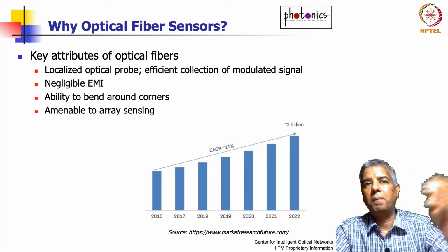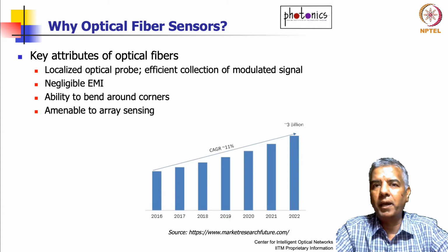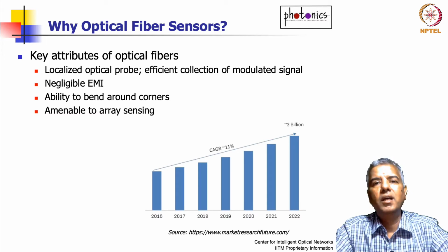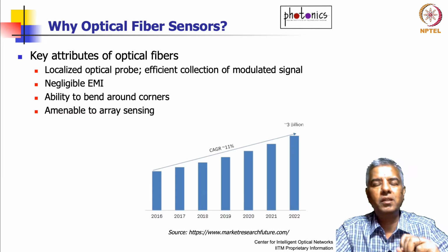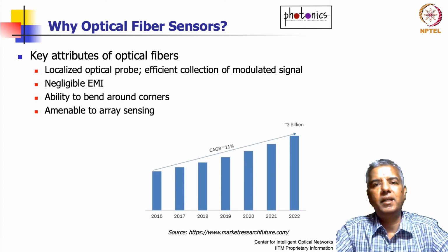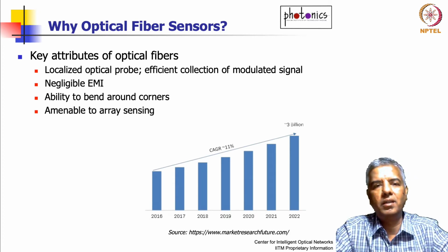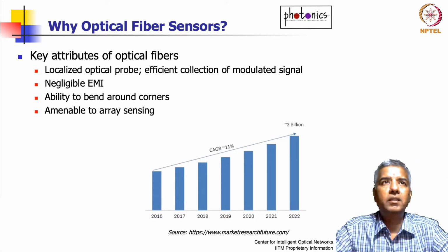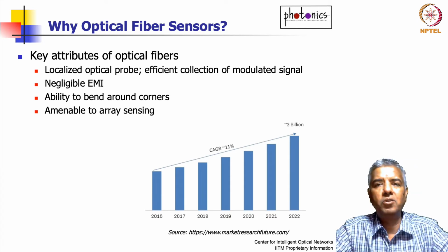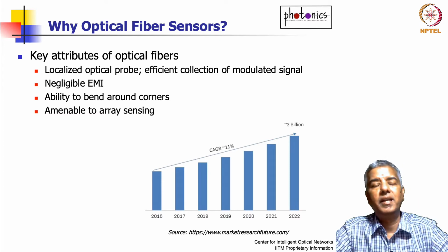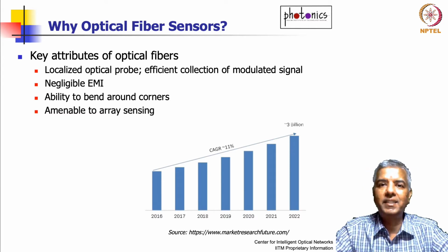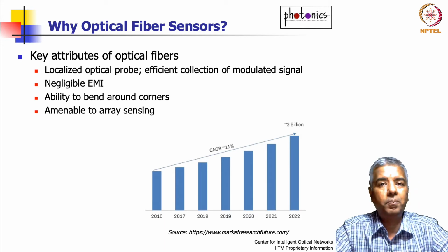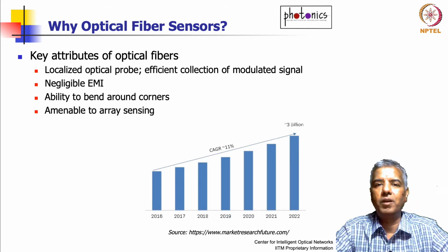Let's say the fiber is deployed along an oil or gas pipeline that's going over several tens of kilometers. So it can pick up information with 1 meter spatial resolution all along the length of the fiber, and provide you that information at the terminal equipment. So typically we're talking about, let's say, a 10-kilometer distance, you have 1 meter spatial resolution, you're talking about 10,000 sensors that are concatenated in a single optical fiber. So that could be the power of this technology, the optical fiber sensor technology.